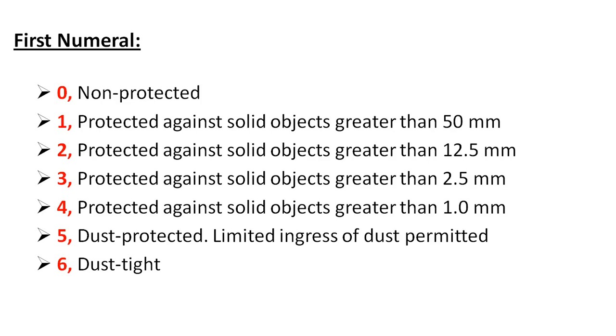If the first numeral is zero, it indicates non-protected — it cannot give any protection against solid objects. If it is one, it is protected against solid objects greater than 50 mm, so a hand or operator's hand falls under this category. Two means protected against solid objects greater than 12.5 mm, so operator fingers fall under this category. Three means protected against solid objects greater than 2.5 mm, so screwdrivers and other maintenance tools fall under this category. Four means protected against solid objects greater than 1 mm; cable wires fall under this category.